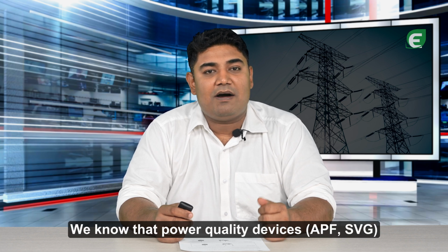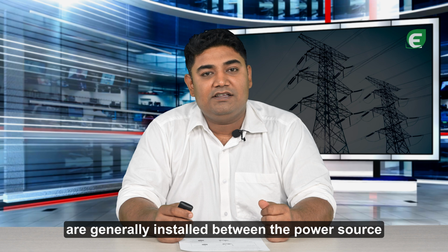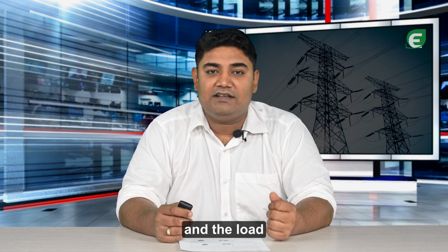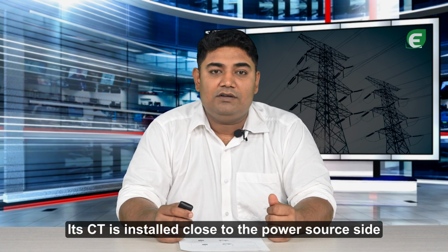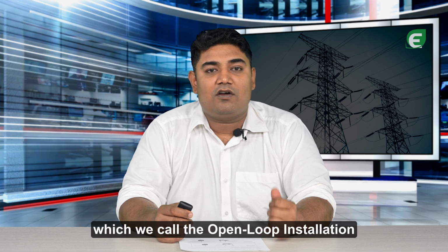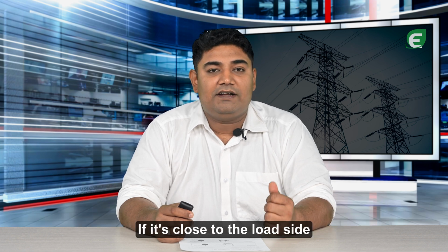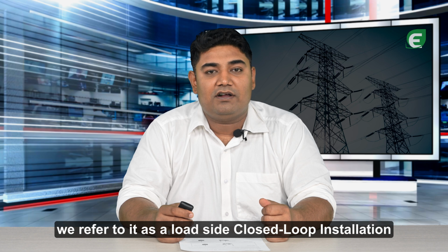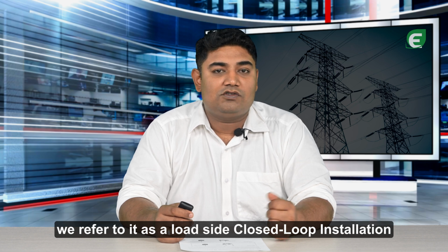We know that the power quality devices are generally installed between the power sources and the load. Its CT is installed close to the power source, which we call the open loop installation. If it is close to the load side, we refer to it as load side closed loop installation.